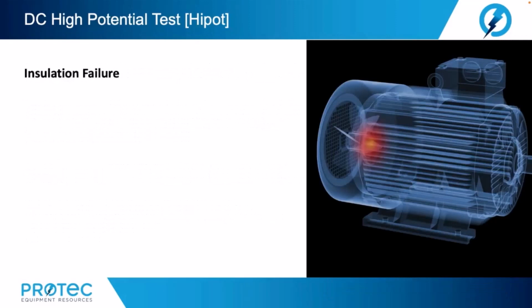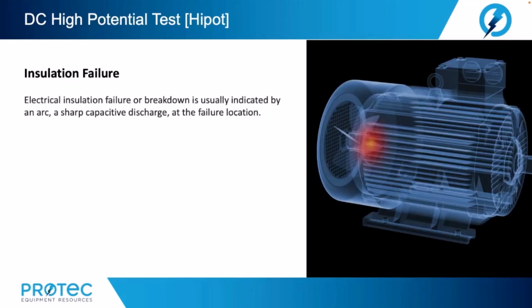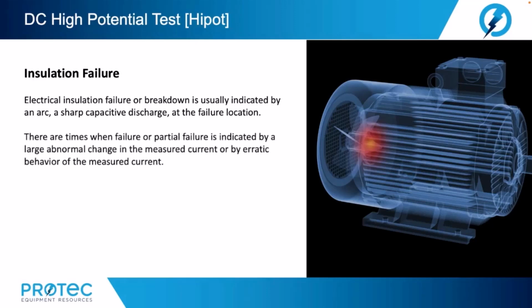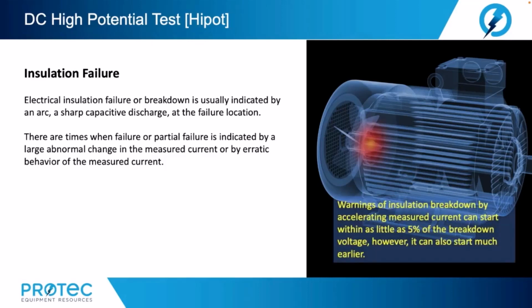All right, let's look at insulation failures. Electrical insulation failure or breakdown is usually indicated by an arc, a sharp capacitive discharge at the failure location. There are times when failure or partial failure is indicated by a large abnormal change in the measured current or by erratic behavior of the measured current. Warnings of insulation breakdown by accelerating measured current can start within as little as 5% of the breakdown voltage. However, it can also start much earlier.